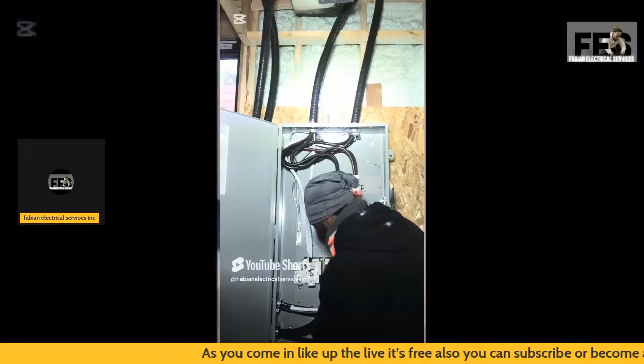You will also see me have the cables wired up into the lugs of the main disconnect, the 400 amp disconnect service that I'm working with, and the cable that I used was 250 kcmil parallel runs.